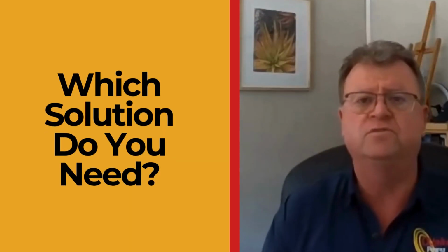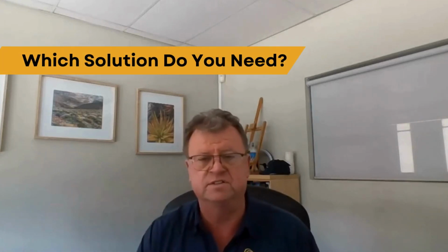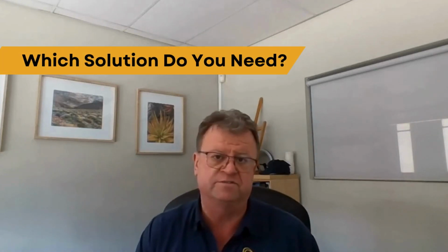So the only way to know exactly what's required on a particular site is to put a high-speed power quality recorder for a period of approximately 1 week. With that data, we're able to design the right solution for our customers, whether it's simply a power factor correction system or a power factor correction system fitted with harmonic blocking reactors, or purely an active filter or a passive filter, or a combination of the two.